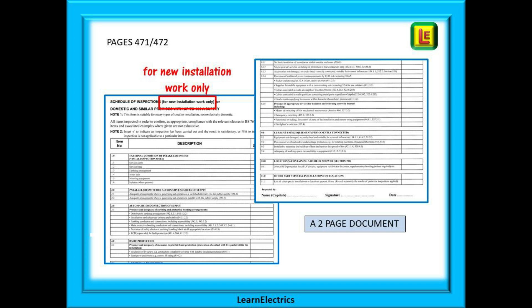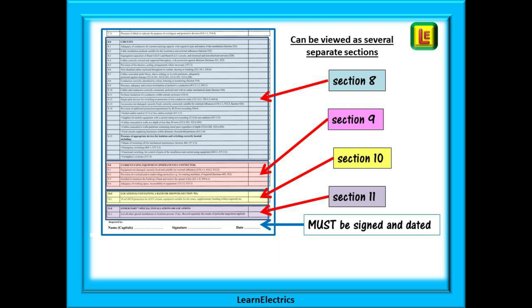The first thing to notice is the very first line: 'For new installation work only.' This schedule of inspections is for initial verification work only. If you add a new circuit to a property, for example, this is the form to use when you inspect the work that you have done. This form is not to be used for periodic inspections — they have their own forms.